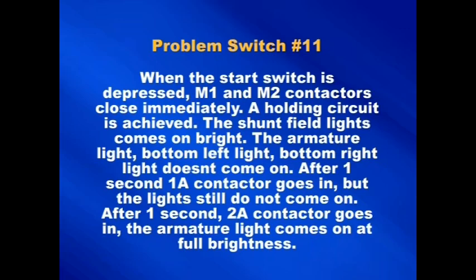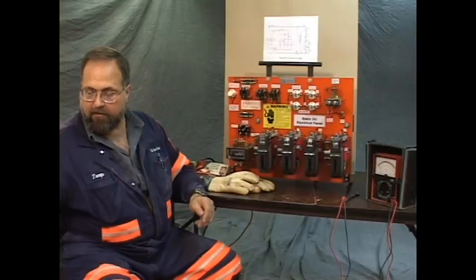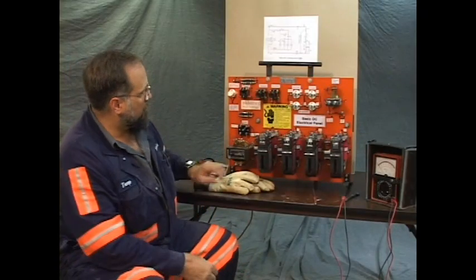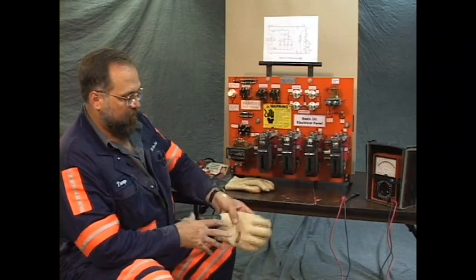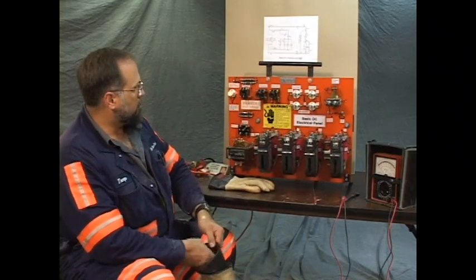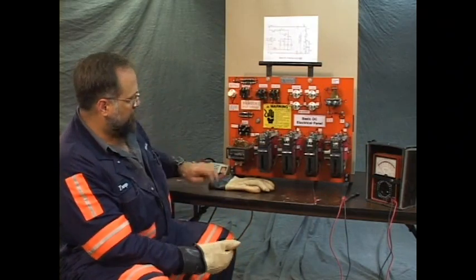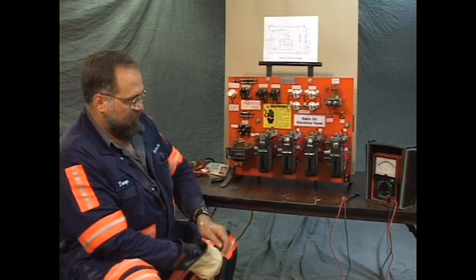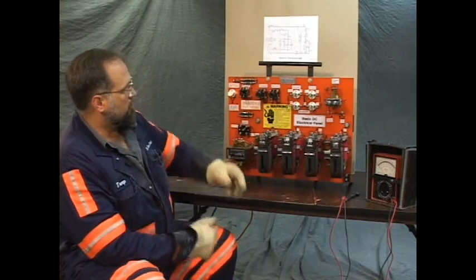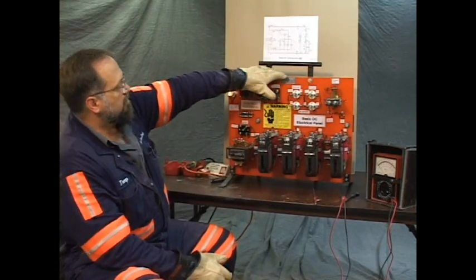After 1 second, the 1A contactor goes in. The lights still do not come on. After another second, the 2A contactor comes in, and the armature light comes on at full brightness. Let's glove up, and we'll show how that problem looks. We'll do normal operation first. To remind everyone of what we're supposed to see.